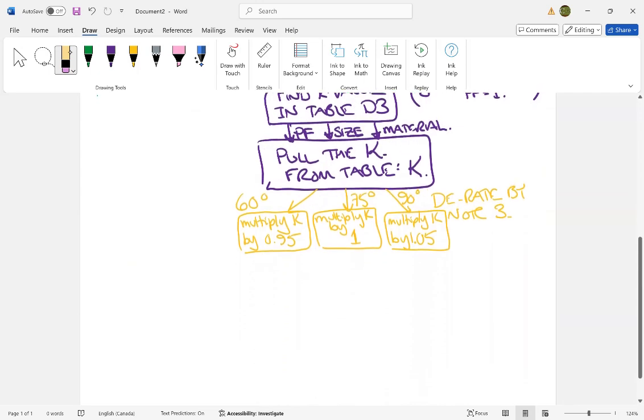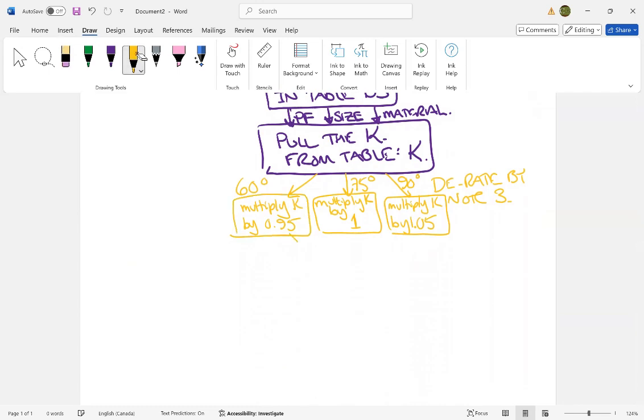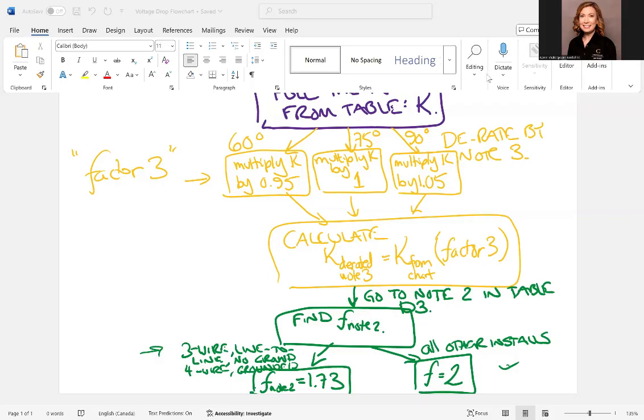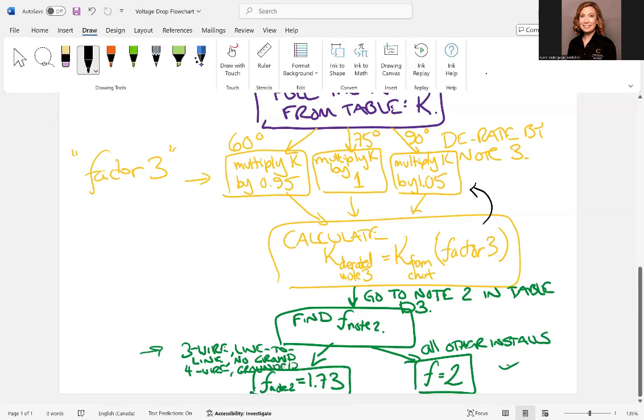So now we get K derated by note three. I'm going to then put these in here and say, calculate K derated three is equal to K from the chart. Then it's multiplied by factor three, which we got from here, 0.95 or 1 or 1.05.